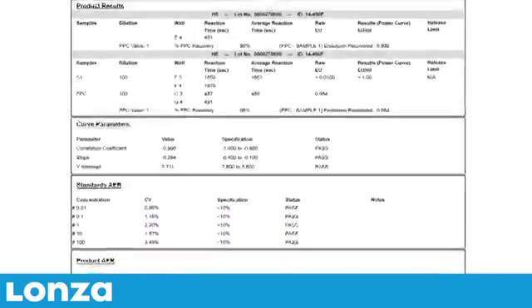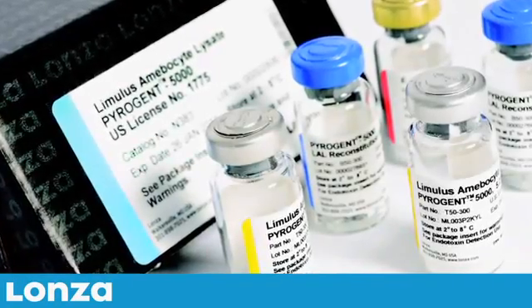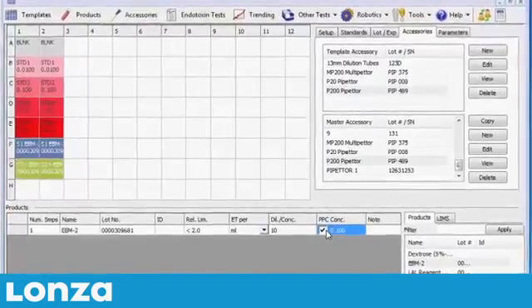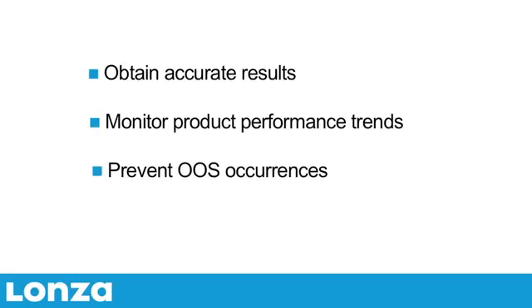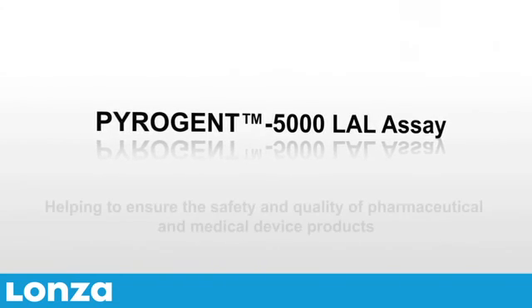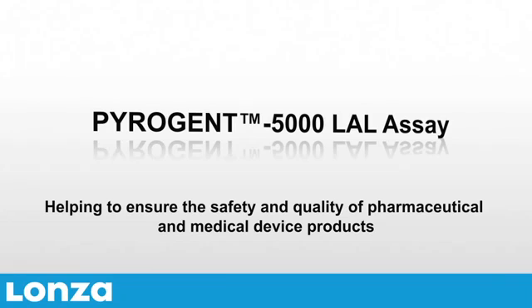The endotoxin concentrations for the unknown samples are then read from the standard curve. Our Pyrogent 5000 Kinetic Turbidimetric LAL assay coupled with our WIN KQCL software are the ideal system for endotoxin detection. Obtain accurate quantitative results when you need them. Monitor your product performance easily by using our built-in trending feature. This will allow you to detect deviations more readily so that you can respond before out-of-specification results occur. Pyrogent 5000 LAL Assay — helping to ensure the safety and quality of pharmaceutical and medical device products.